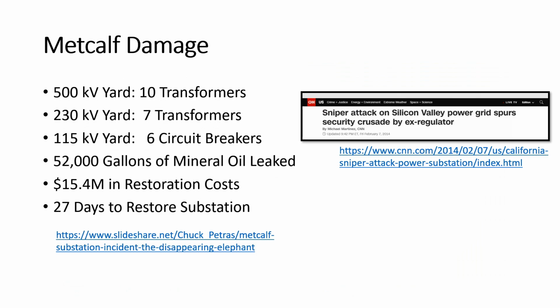In summary, the damage identified following the shooting was 10 transformers shot, 7 in the 230 kilovolt yard, and 6 circuit breakers shot in the 115 kilovolt yard. I talked about the 52,000 gallons of oil. Restoration costs were about $15.4 million, and it took 27 days to restore the substation.